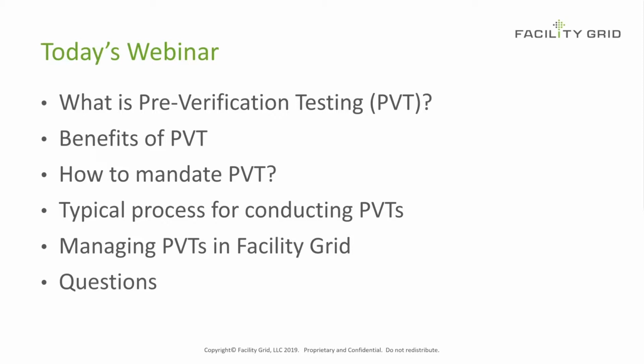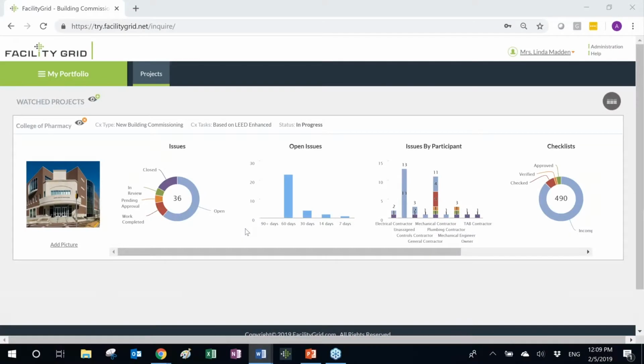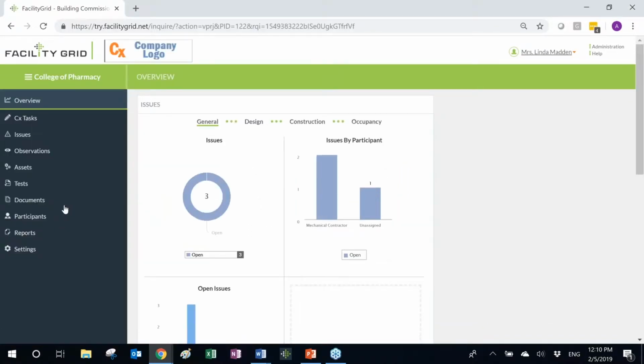Basically, the goal is to address any concerns ahead of the functional performance tests conducted by the commissioning agent. Now let's take a look at how this process can be managed in Facility Grid. I am now logged into Facility Grid as a controls contractor. So let's assume I would like to conduct a pre-verification test for an air handling unit. So I'm going to click on the project icon and get to the project.